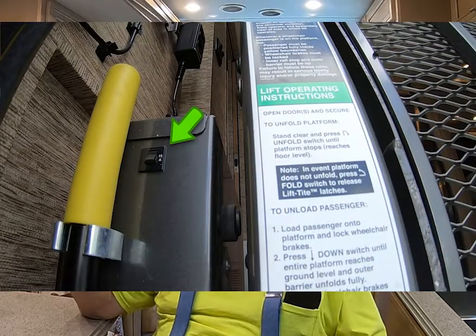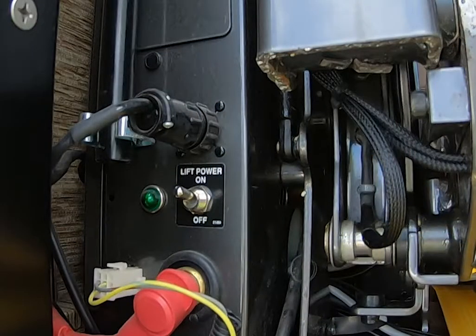Some of the analysis you can do initially: are the lights on, are the lights off? If the lights are on, the unit has power. If the lights are off, you've got an interruption to that power somewhere. It could be the circuit breaker on the unit, shown here, or one of the limit switches the coach builder has installed—in this case Newmar—for gear shift, ignition switch, or door. It could also be the chassis battery or its circuit breaker. If the lights are off, you also need to check whether the on-off switch itself is simply switched off.